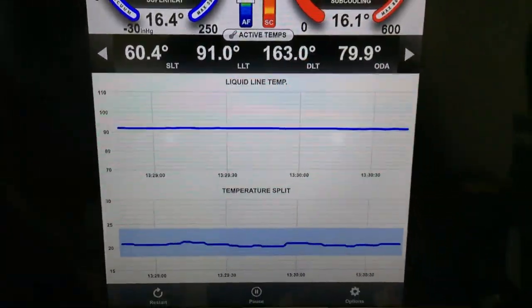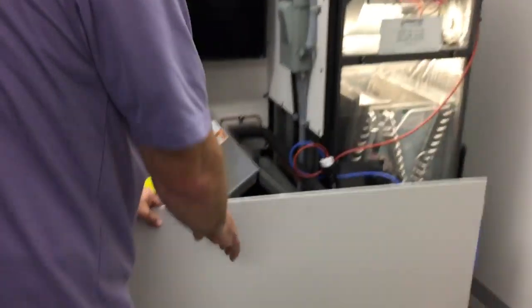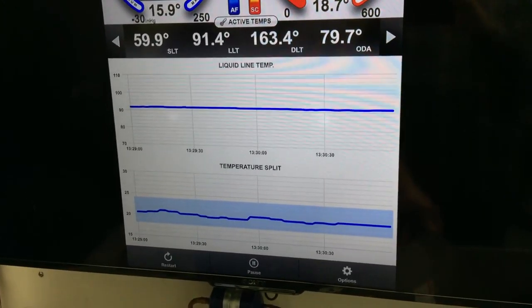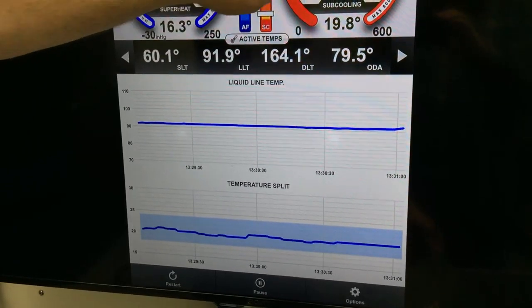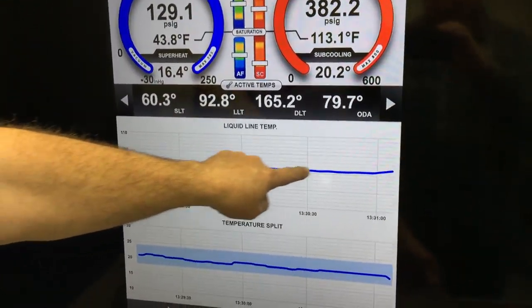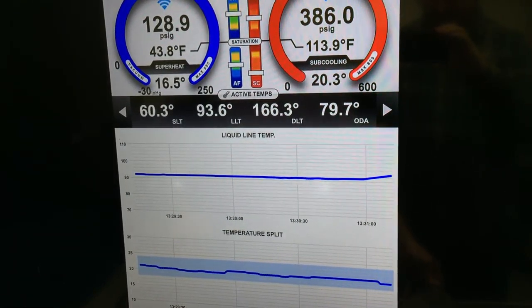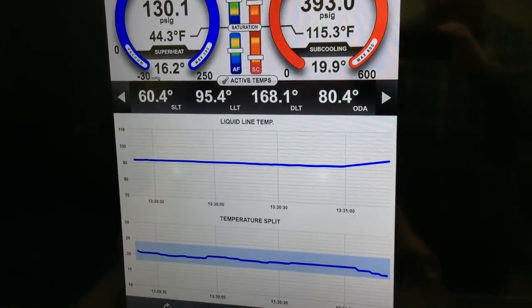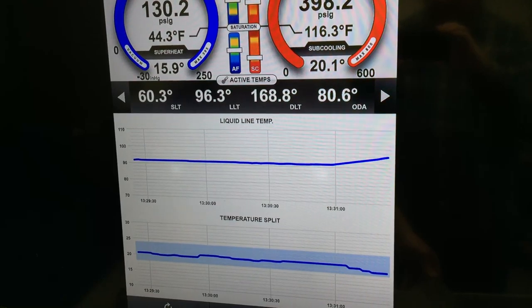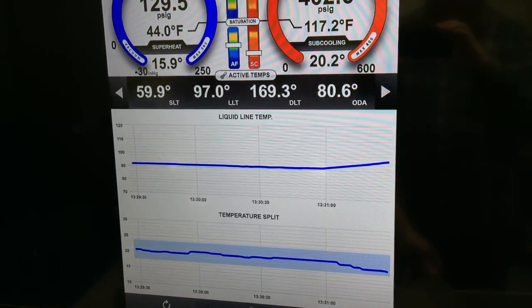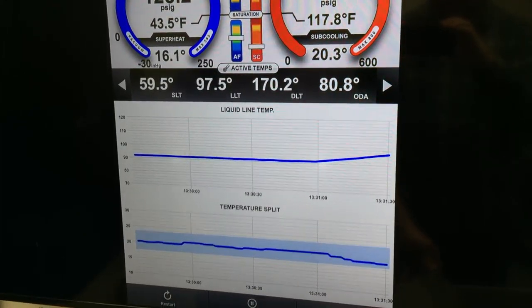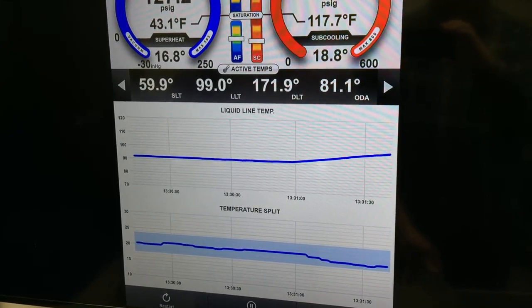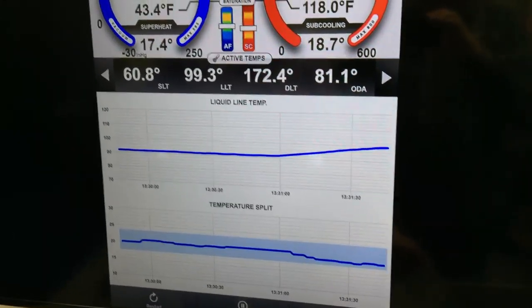What I'm going to do here is go back into the app for just a minute, take a piece of cardboard here, and I'm going to block off our condenser a little bit more. It's obviously going to destabilize the system and things are going to change. You can see our head pressure is going up right here, and you can see our liquid line temperature is trending up, and we'll let that run this way for just a few minutes here to get things stabilized. Whenever you're making changes to a refrigeration system, it takes a few minutes. You can't immediately evaluate performance because the refrigerant has mass, and that mass of refrigerant takes time to heat up. So the heat that we're not rejecting right now is actually warming up all the liquid in the condenser and in the system. And as that liquid is getting warmer and warmer, as we're seeing that liquid line temperature rise up, you'll notice also a trend happening right here — our temp split is actually starting to drop down. So we're going to give that a couple more minutes and let that stabilize and see where we end up.